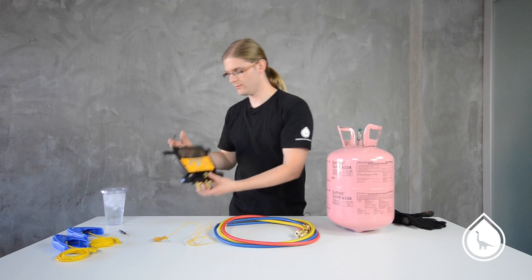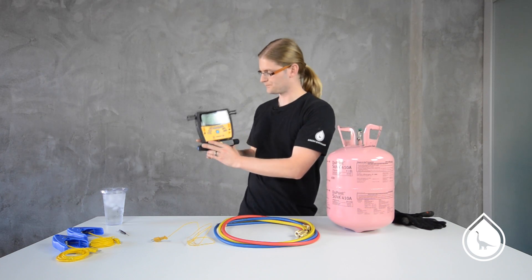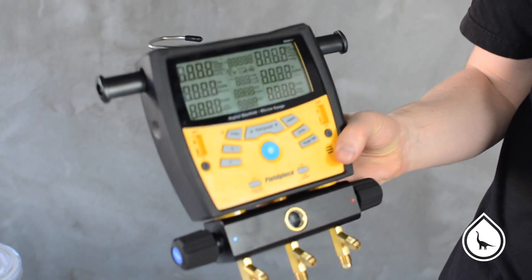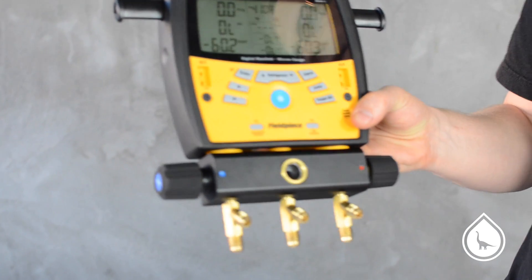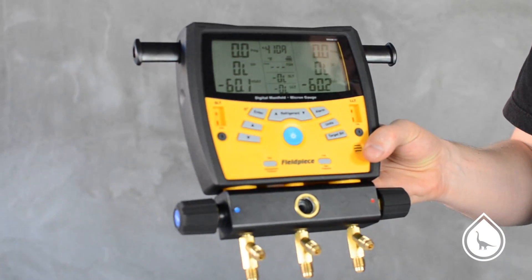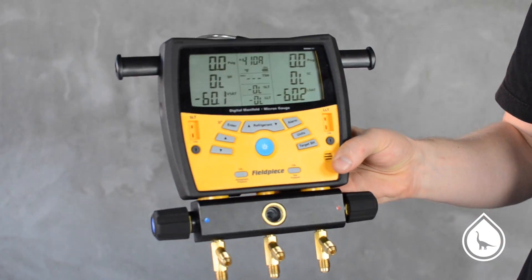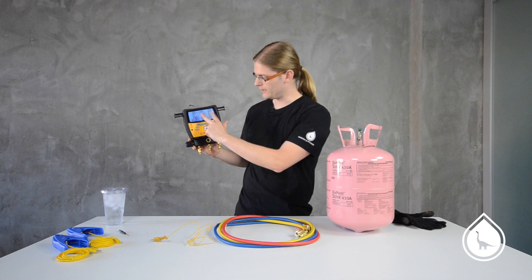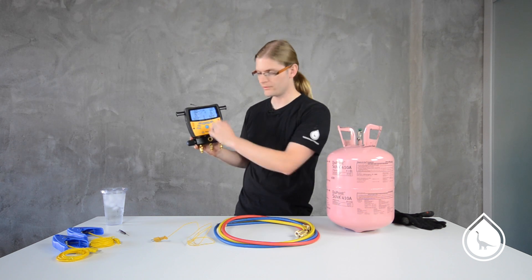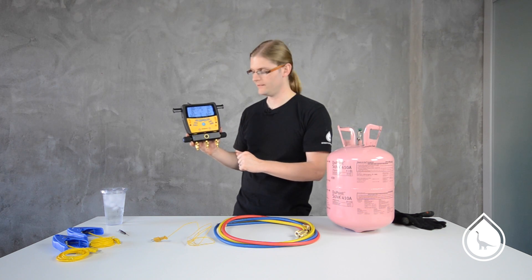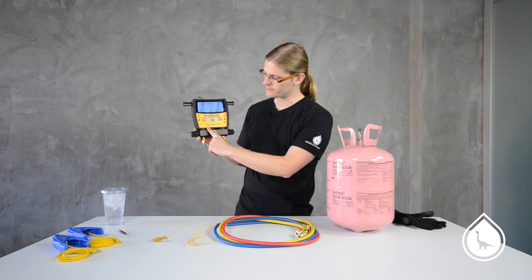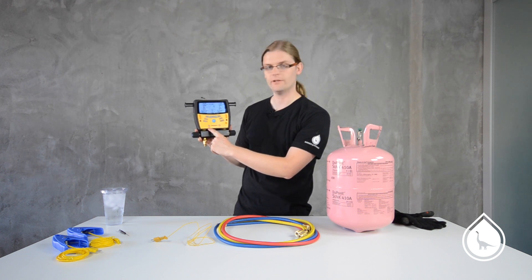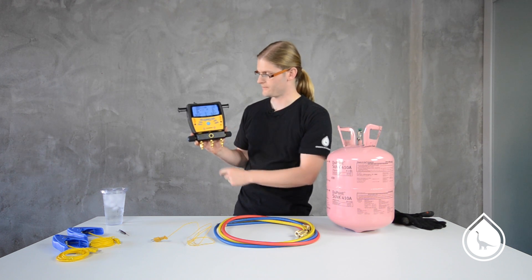So to get started, first thing you want to do is turn the gauge on and check that the pressures are reading zero with no hoses attached and open to the atmosphere. We're in good shape here. They're both reading zero. If we had anything there, we would zero it out by pressing the calibrate atmospheric pressure button down at the bottom.